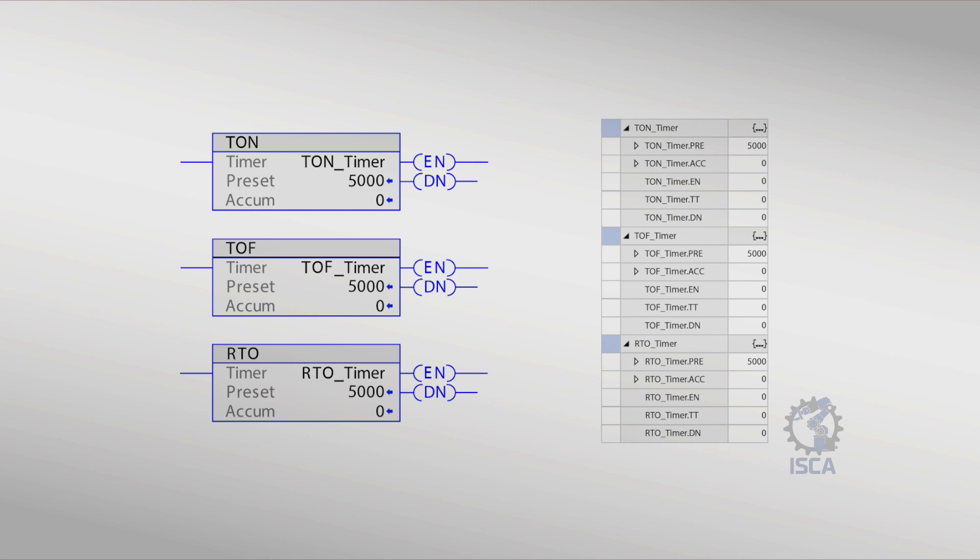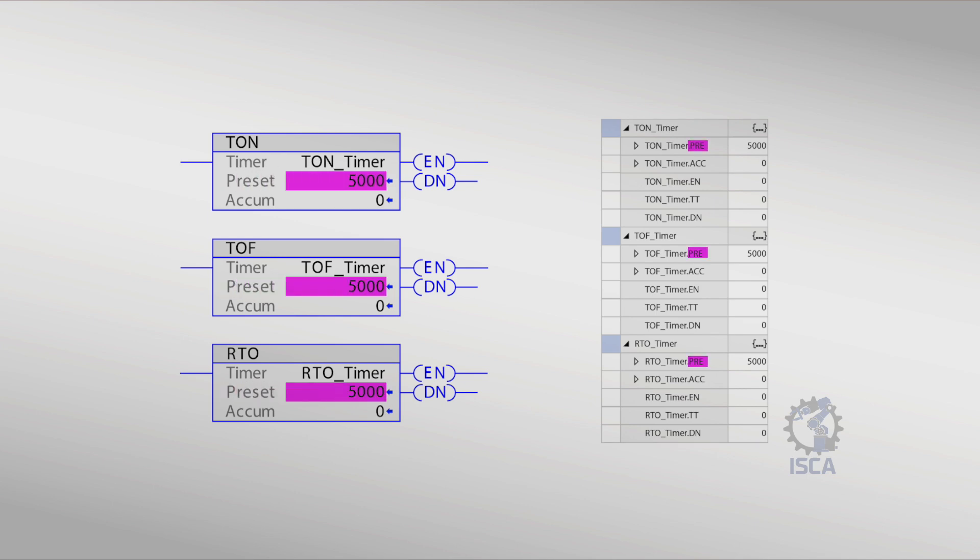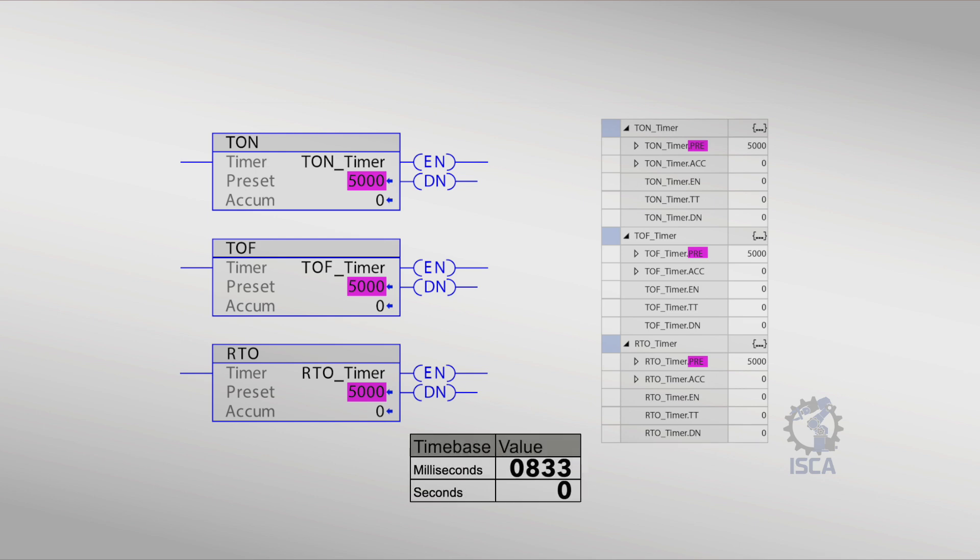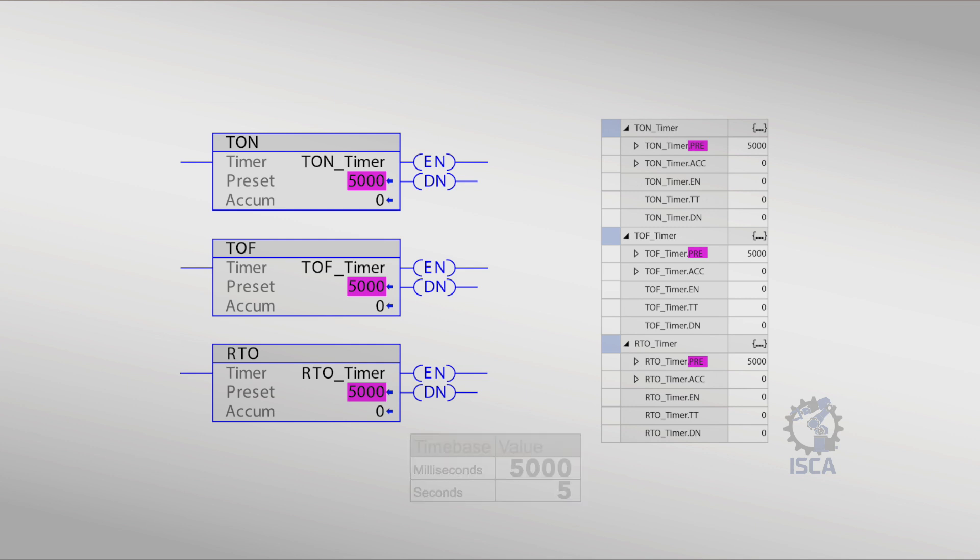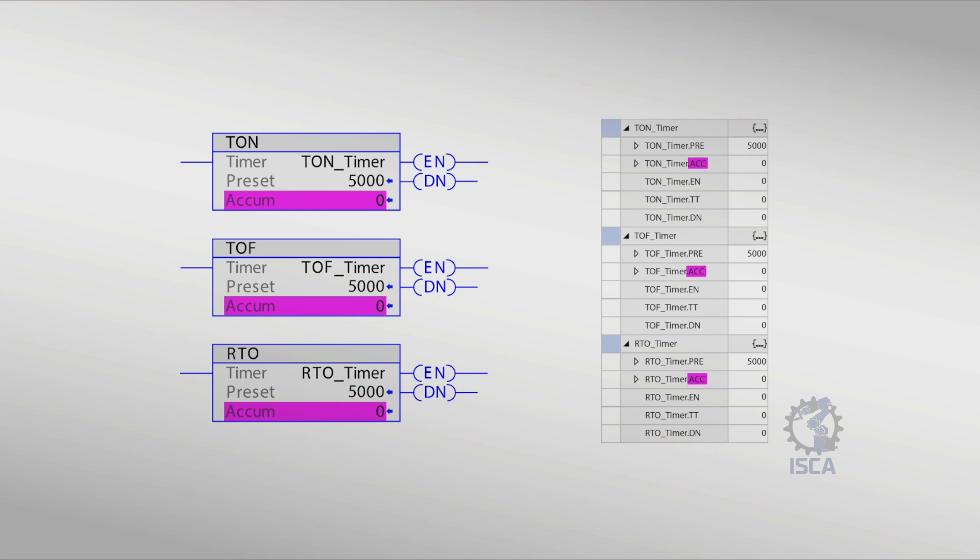Timers have bits and parameters that include preset time, PRE. This is the time or value the timer must accumulate to reach the desired time delay. The time base is 1 millisecond, meaning 1000 will be 1 second. Accumulator, ACC, is the value the timer has timed so far after it has been enabled.